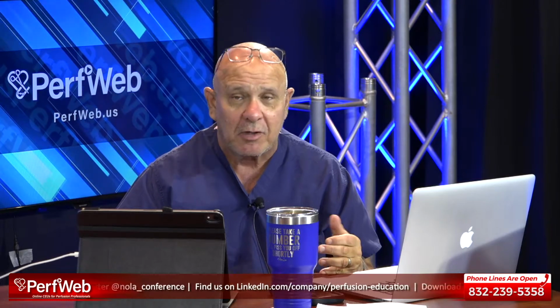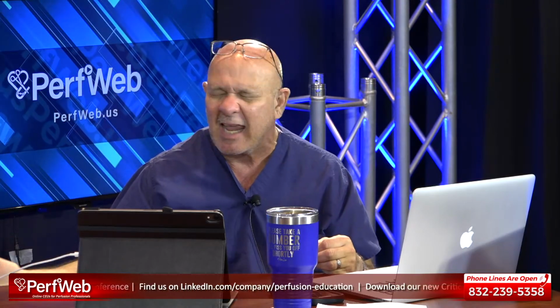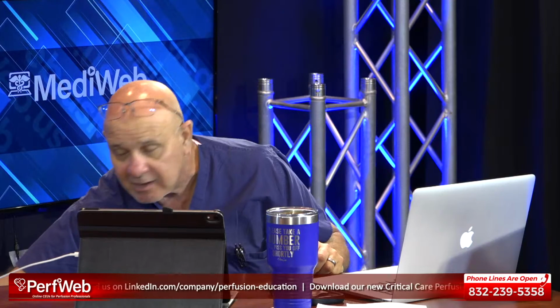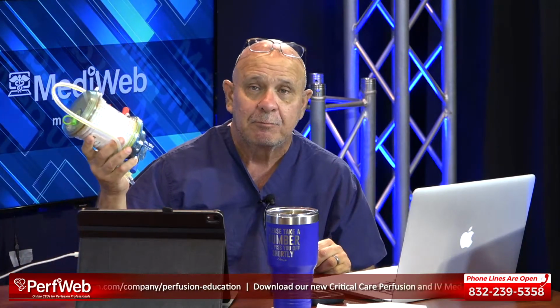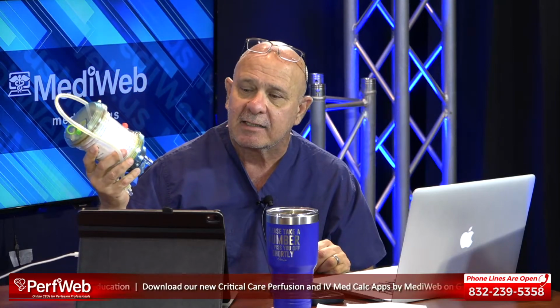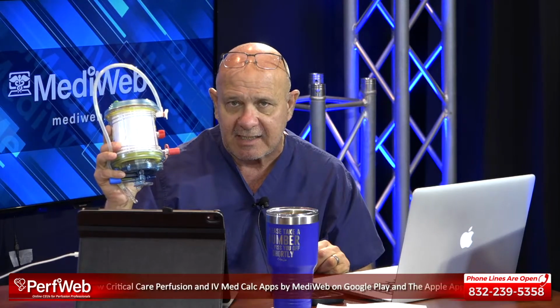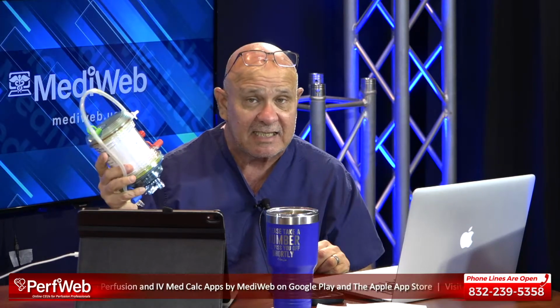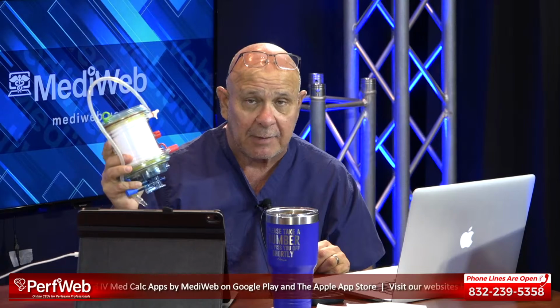And it's not going to be possible to flow 8 liters with this oxygenator. You can, but it's not going to work very well. The pressure drop is going to be too high, and it's not going to be very efficient in terms of its gas exchange. You may need a separate system in order to be able to do that.